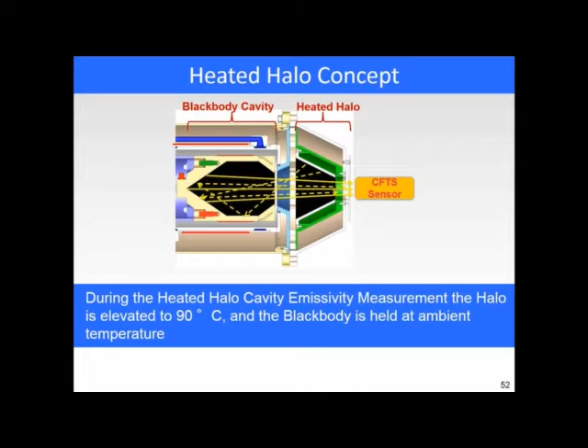Times 1 minus the emissivity of everything else, which is a view factor that the cavity has to the cone, plus 1 minus that view factor times the background. So basically, everything in this equation is known. But there was one problem, and that is that our pyroelectric detector has a very, very low signal for this measurement. And so we have to integrate over a long period of time, which means we can't let the instrument deviate in temperature or it would just wash away the signal.